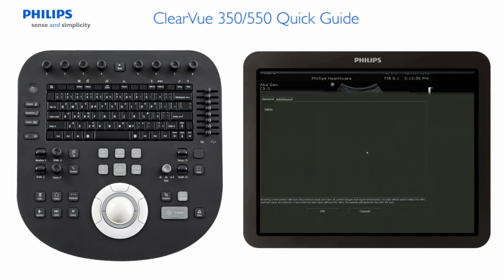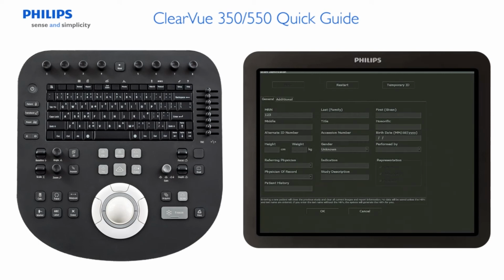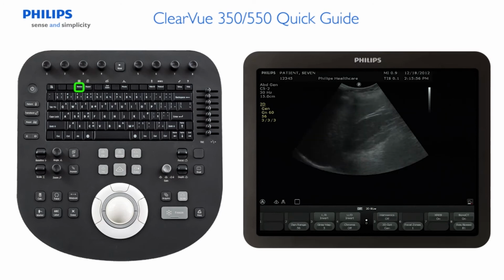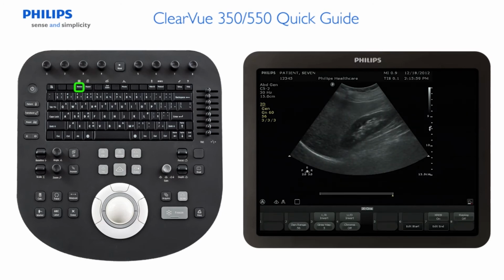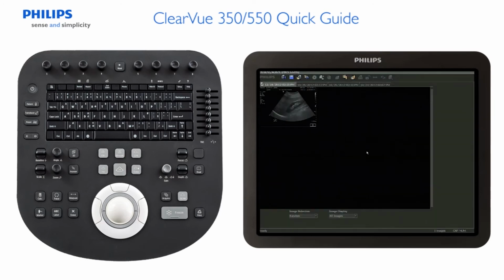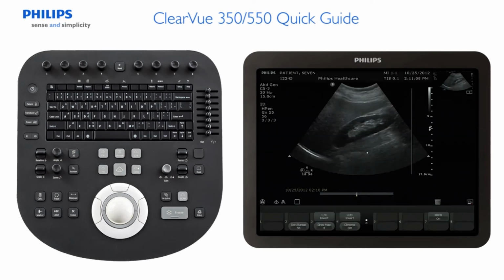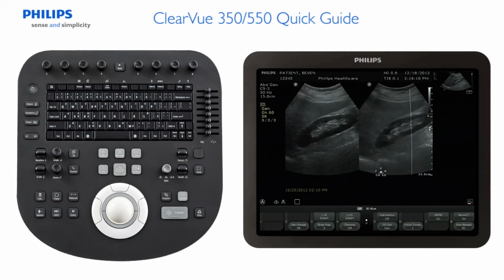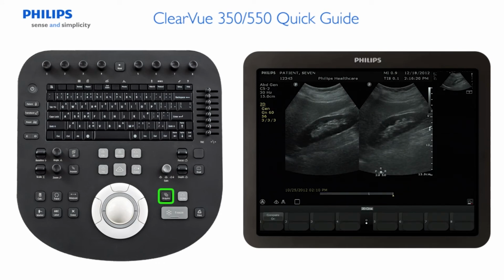First, we begin by entering the patient data. Next, we acquire an image, then press the Review key. Select the previous study, and then double-click on the image you wish to compare. Press the Next key, and then press the Compare Quick key. The review image is displayed on the left, and the live image is displayed on the right. Please note that if you press Acquire while in Compare, only the live image is acquired.